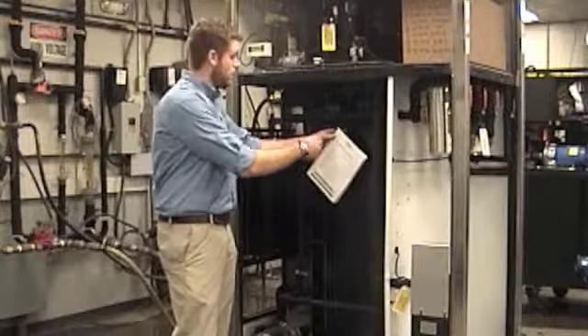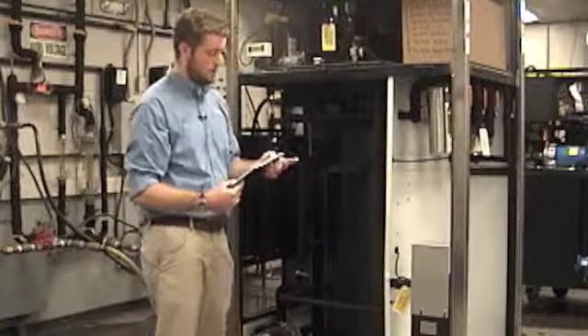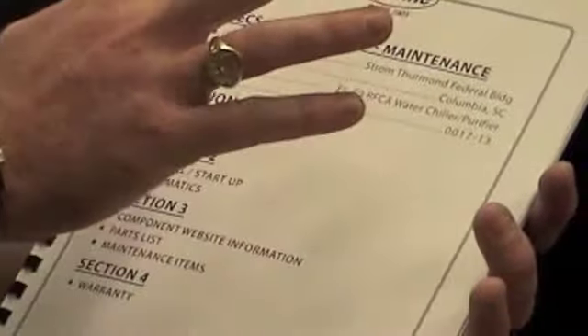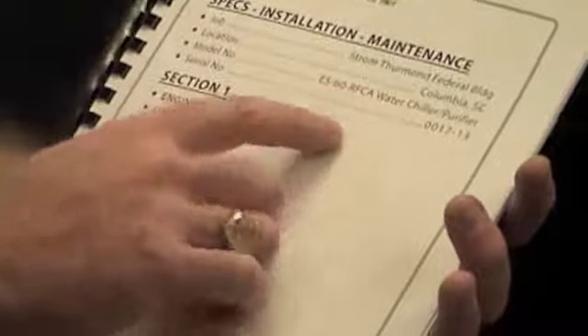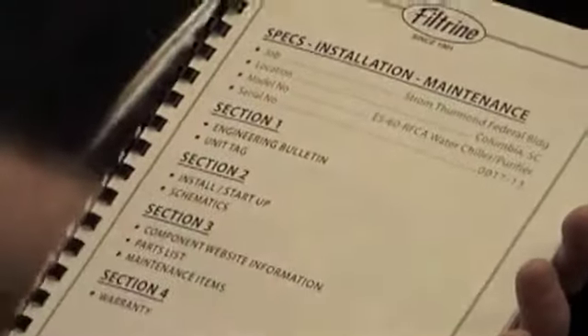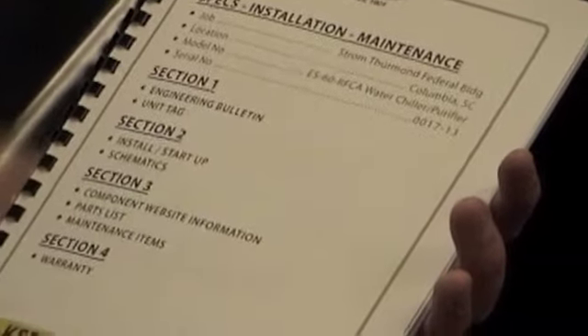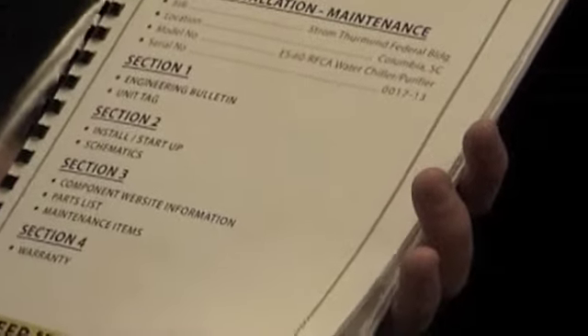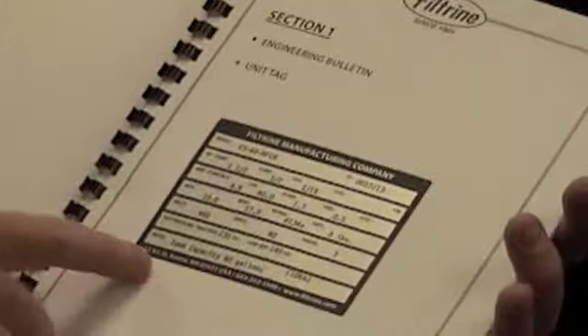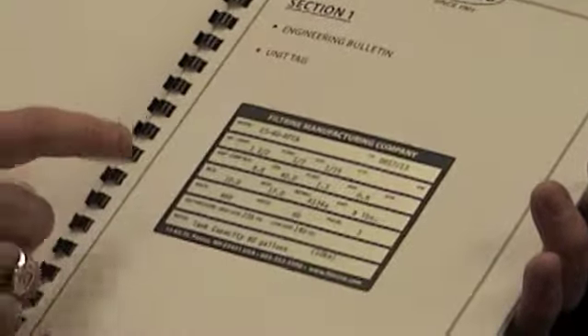Right in here is where you'll find your manual. You can simply use your wire cutters to clip it out. Inside your manual, you'll have your pertinent chiller information, the location of the chiller, its model number, obviously the serial number. Serial number is important to keep track of in case you ever need to call the factory for warranty information or for parts. We have a record of each chiller. Inside, you'll have a copy of your unit tag, which will give your amperages, your voltage, and some of the other technical information on the unit. Followed up by the more detailed information on the components of the chiller.